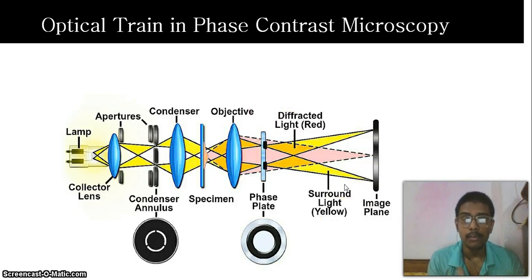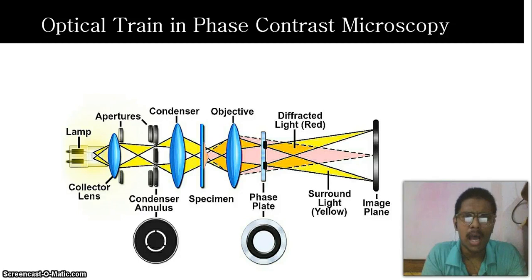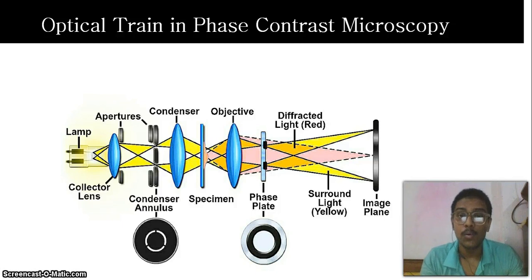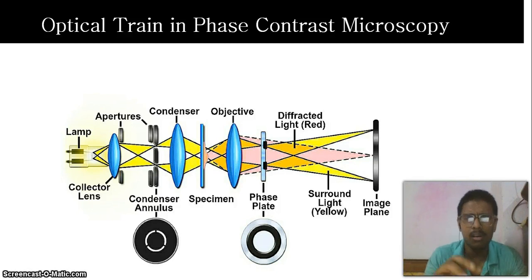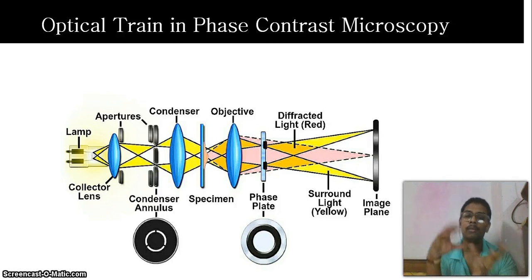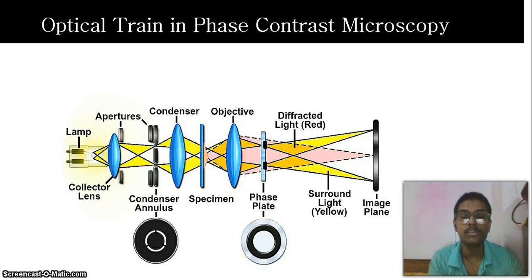The undiffracted light doesn't contain any information from the specimen. That's why scientists thought: 'I can't use undiffracted light as an information carrier for the specimen, but I can use it to increase the contrast, to make the image quality better.' So they used the undiffracted light — which doesn't carry any information — to increase the image contrast. This is done using a special phase plate, which works quite similar to the condenser annulus, to make a phase difference with the diffracted light. This is recorded in the image plane to make better contrast, helping you investigate every minute detail of your specimen.